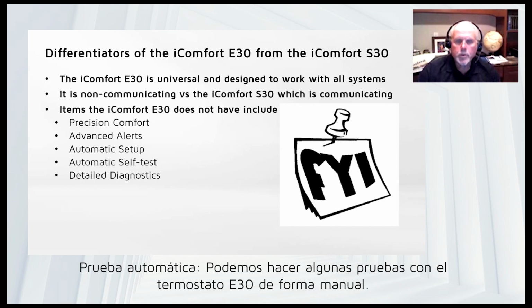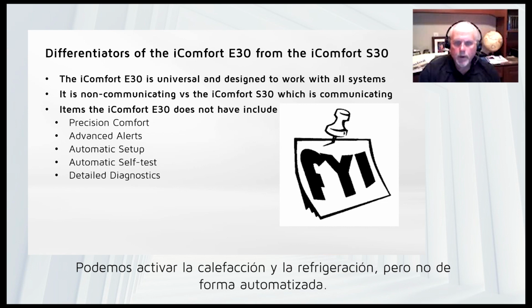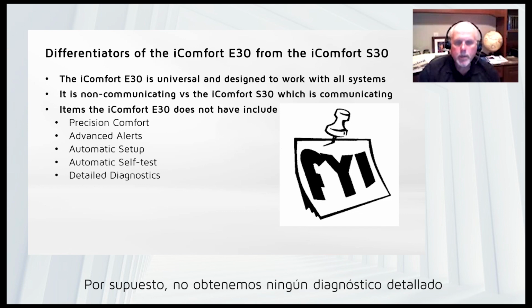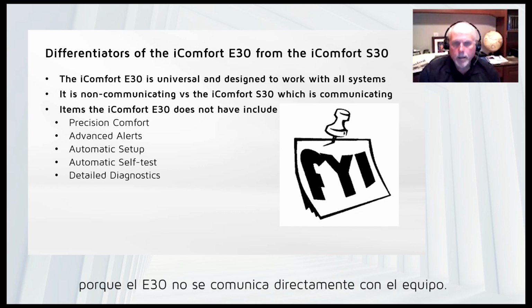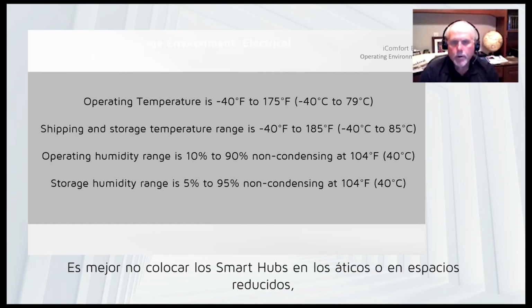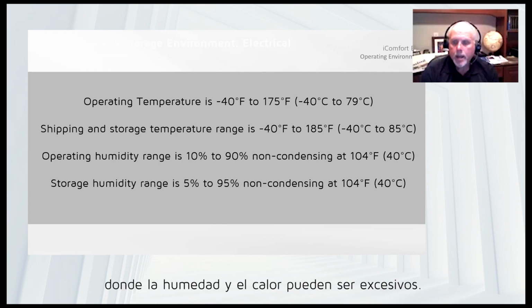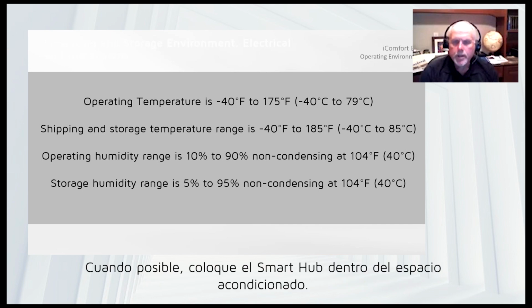Automatic self-test. We can do some tests. We can run heating and cooling calls through tests, but it will not do automated tests. And of course, we do not get any detailed diagnostics because the E30 is not communicating directly with the equipment. It's best not to put the smart hubs in the attics, or maybe in crawl spaces, where moisture and heat can be excessive. So it's better to have those in the conditioned space if you can.